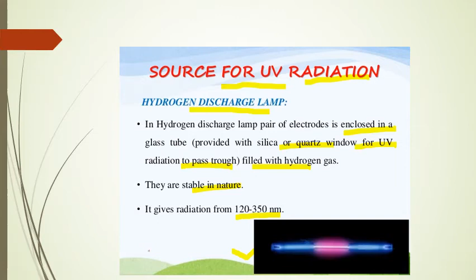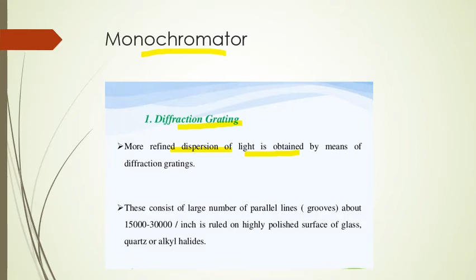So the next feature is the monochromator. Different monochromators are used in the UV visible spectrophotometer. One of them is the diffraction grating. A more refined dispersion of light is obtained by means of the diffraction grating, which consists of a large number of parallel lines or grooves, about 15,000 to 30,000 per inch, ruled on a highly polished surface of glass, quartz, or alkali halides. The prism is also used in the UV visible spectrophotometer, and the prism also diffracts the light, and we have the monochromatic radiation to pass through the sample.